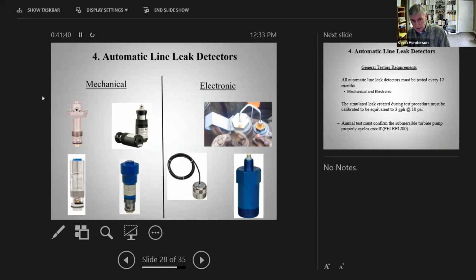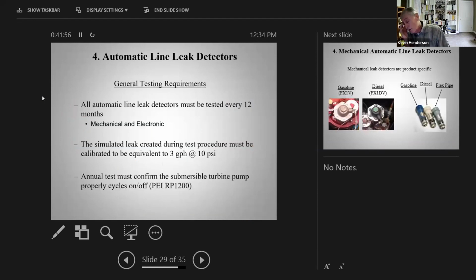But you know, mechanical leak detectors have been around since the 1950s. Electronic leak detectors are a more recent invention, but we have to test both of them at least annually to make sure they are working correctly. And the idea is you can test at 3 gallons per hour, 10 psi leak equivalent. Everybody knows that's the standard. That does not mean you can actually detect a leak of 3 gallons per hour, but it means you can see a hole in the pipe that is equivalent to the size of a hole that will allow 3 gallons per hour to leave if the line pressure were exactly 10 psi. Even that simple concept causes a lot of people a lot of trouble understanding that it's not actually looking at a 3 gallon per hour leak in most cases. We're looking at the size of a hole. That's what the leak detector is capable of detecting, a certain size hole in the pipe.